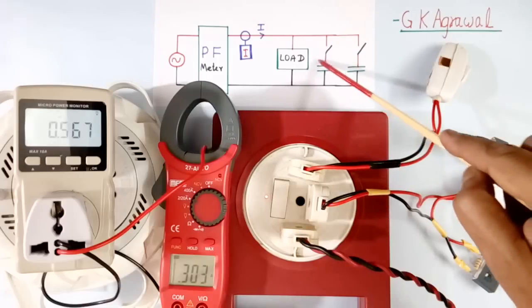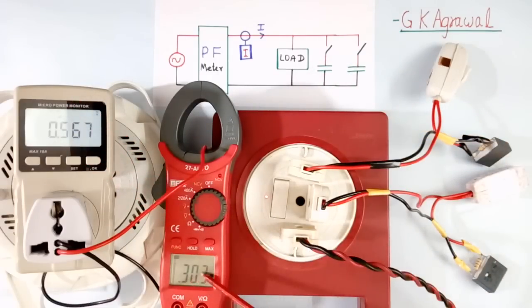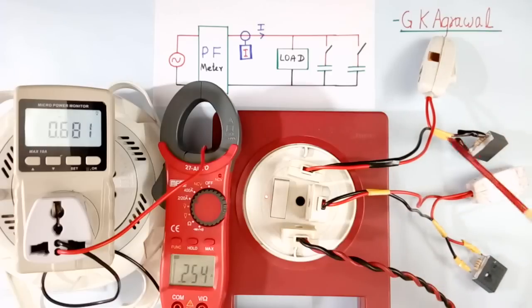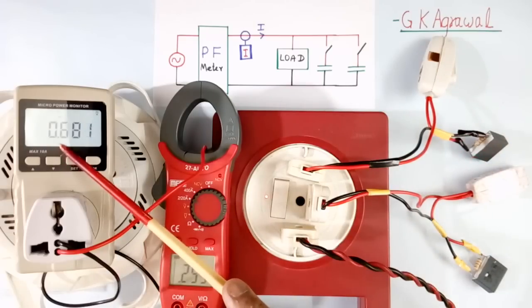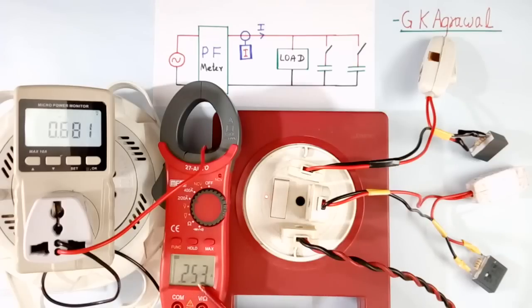Now I will switch this capacitor and see the power factor should improve and this current should reduce. See I have switched one capacitor, this one. See power factor improved to 0.68. And current reduced to 0.25 ampere.